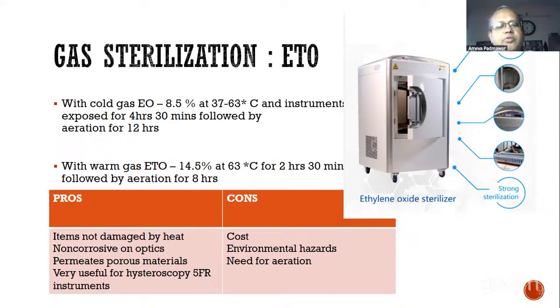There are two formulations available of the canister, and they work at a humidity of 40 to 80 percent humidity and a temperature of less than 60 degrees Celsius. And the instruments are exposed for 4 hours, 4.5 hours. And after the cycle is over, the instruments have to be aerated for about 12 hours. Okay, so the only drawback of this is that being an environmental hazard, the aeration time is 12 hours.